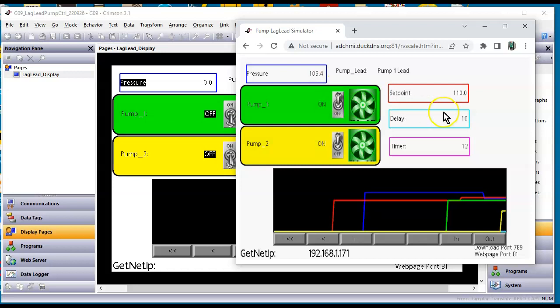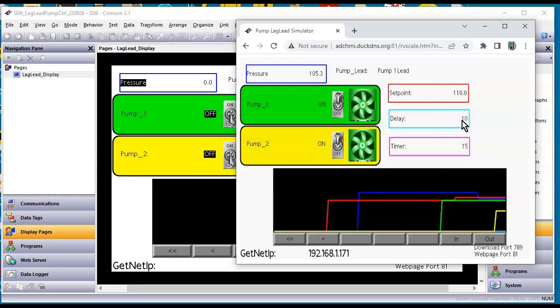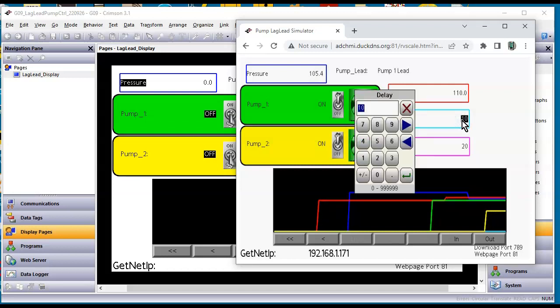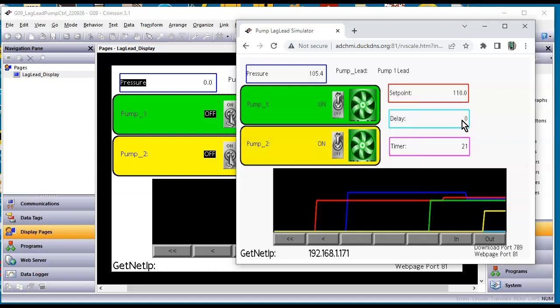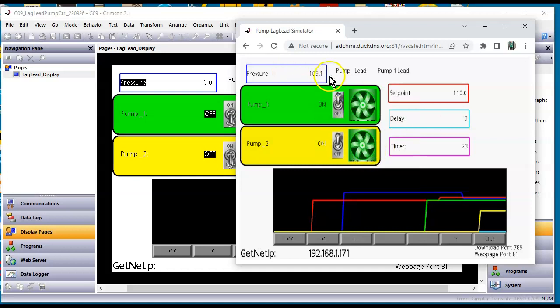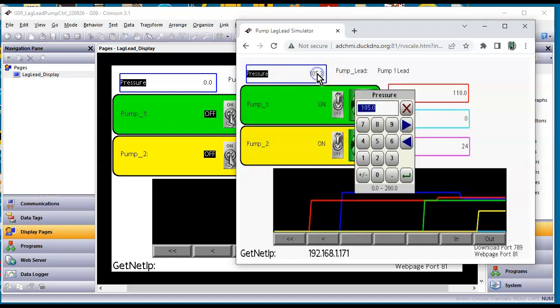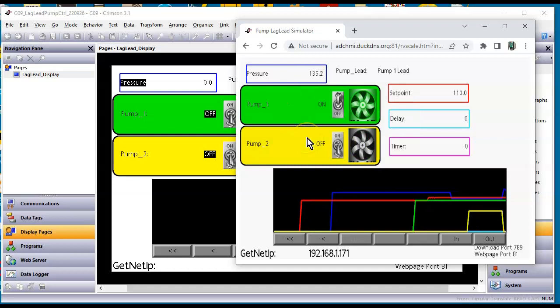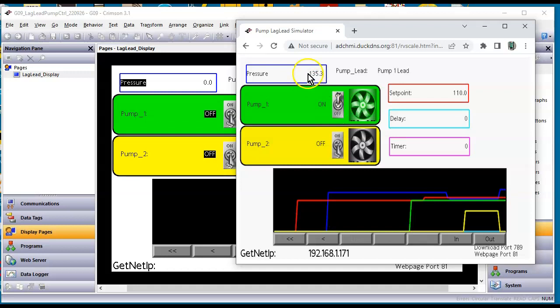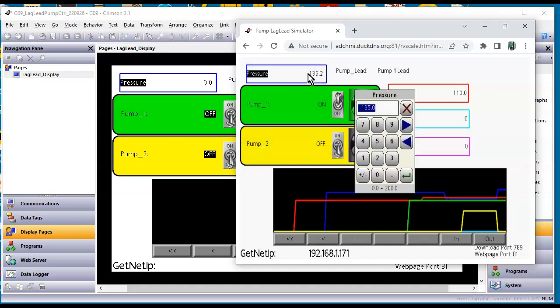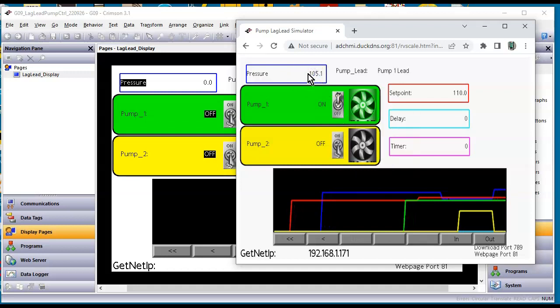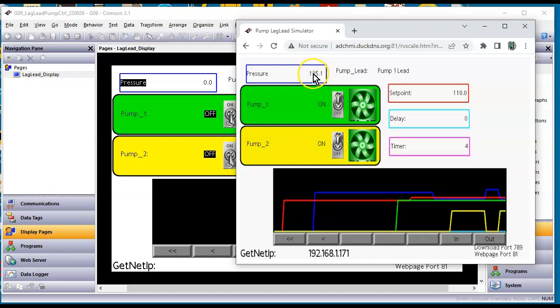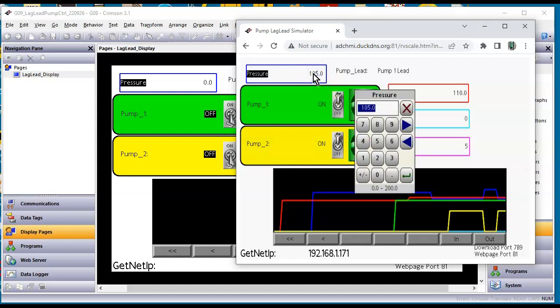Oops well that's fascinating. Oh I forgot about my timer. So there was a little latency there because I had a delay in there. I've got a delay. So at first the guy wanted to put a delay in. If I set this to zero and if we put this back up let's take it to 135. So you can see that pump number two turned off. Pump number one is still running and if I go below that number immediately this guy turned on right away. So I took that delay out of the equation.